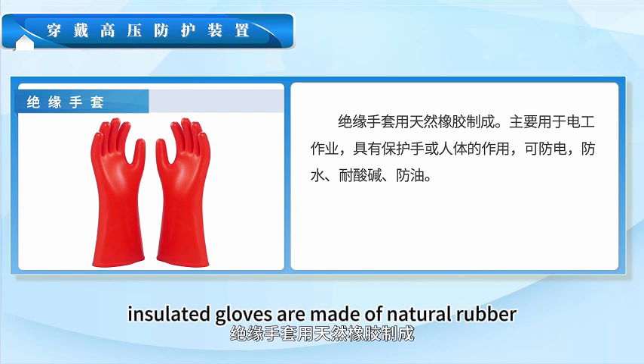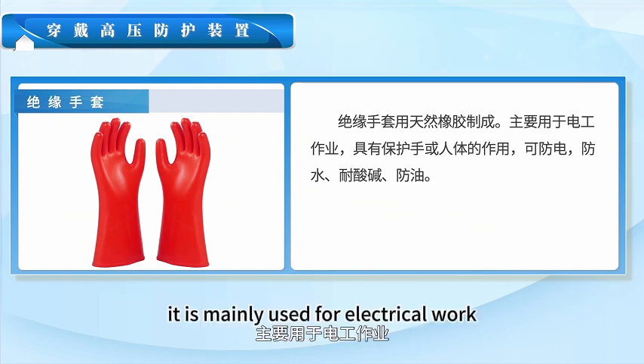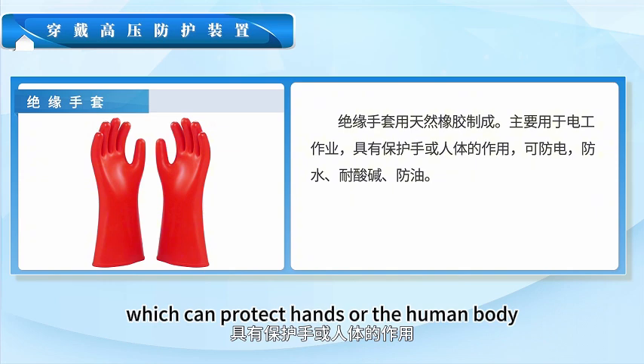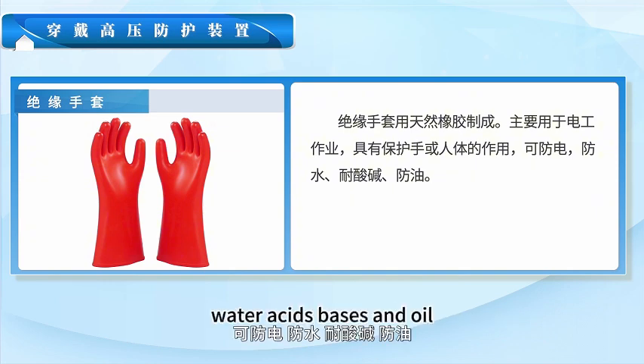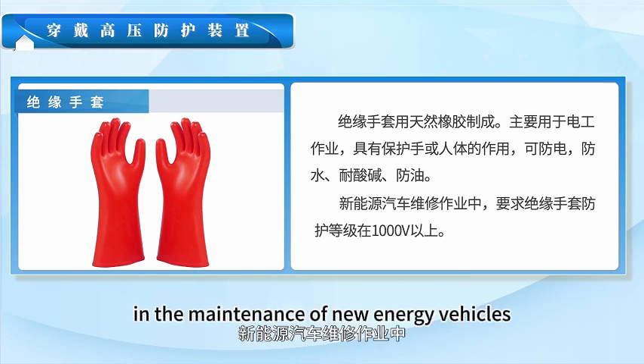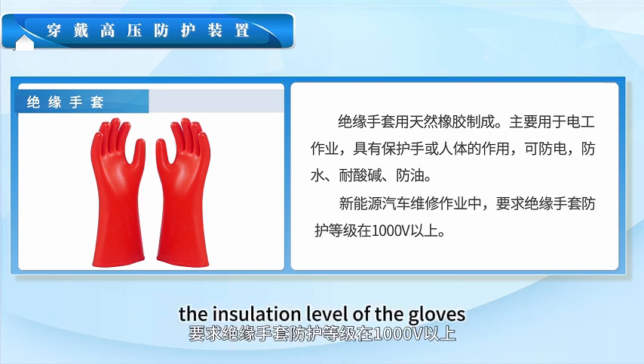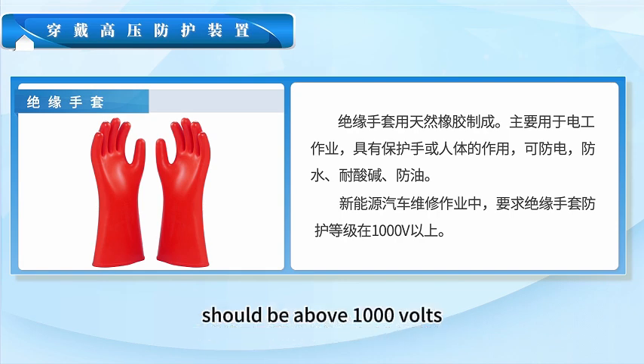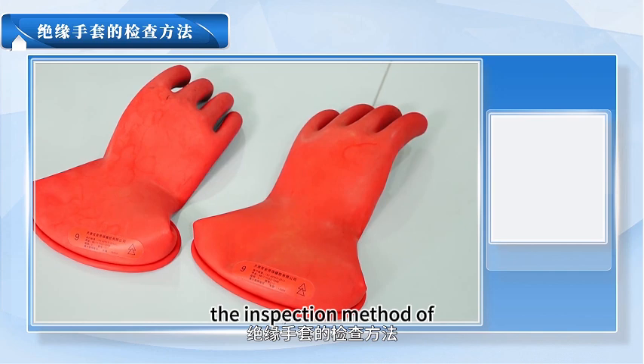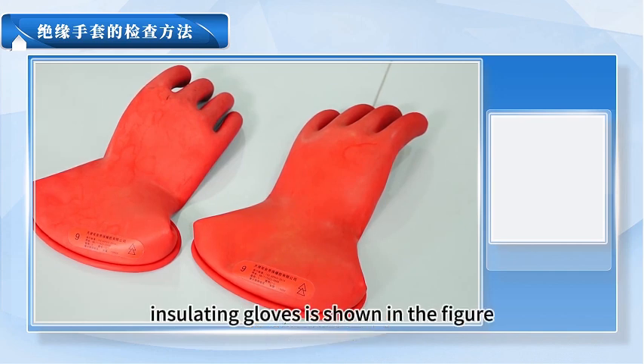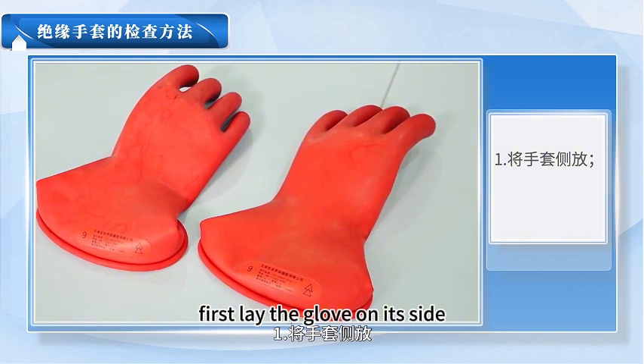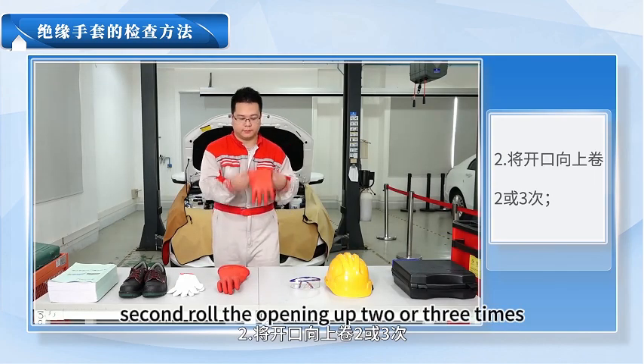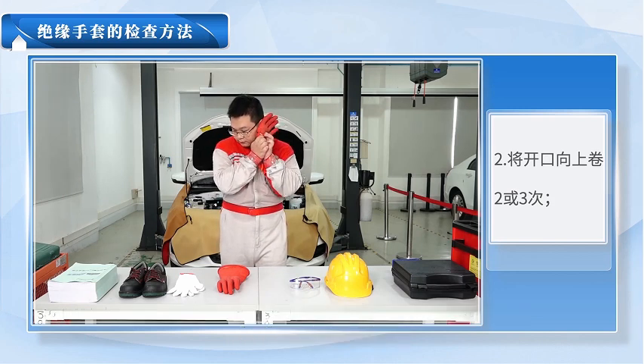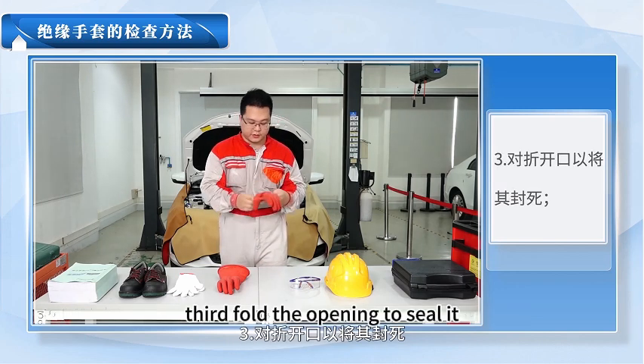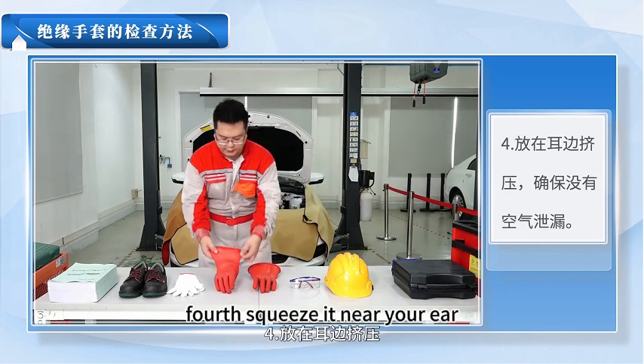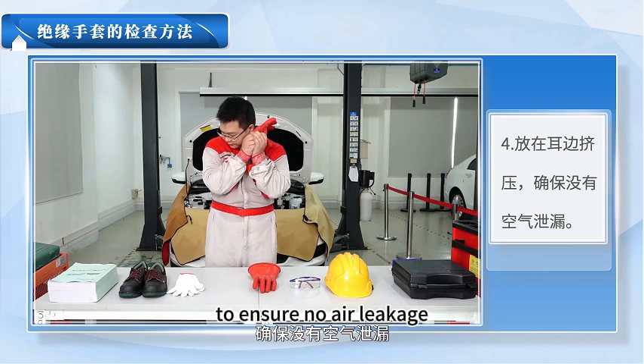Insulated gloves are made of natural rubber. They are mainly used for electrical work, which can protect hands or the human body. They can prevent electricity, water, acids, bases, and oil. In the maintenance of new energy vehicles, the insulation level of the gloves should be above 1000 volts. The inspection method of insulating gloves is shown in the figure. First, lay the glove on its side. Second, roll the opening up 2 or 3 times. Third, fold the opening to seal it. Fourth, squeeze it near your ear to ensure no air leakage.